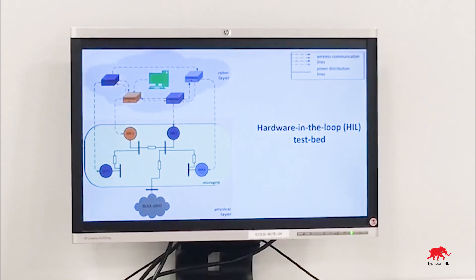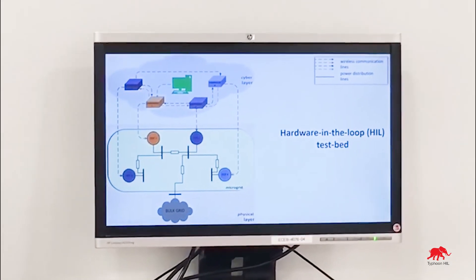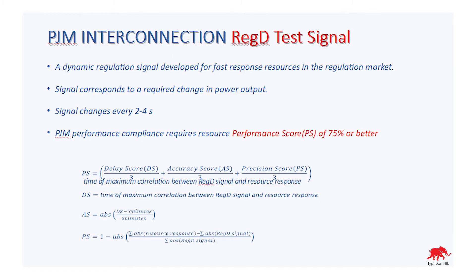The regulation signal we use in this testbed is called the PJM Reg D test signal. It is a dynamic regulation signal developed for fast response resources in the regulation market. The signal corresponds to a required change in power output. The signal changes every 2 to 4 seconds.